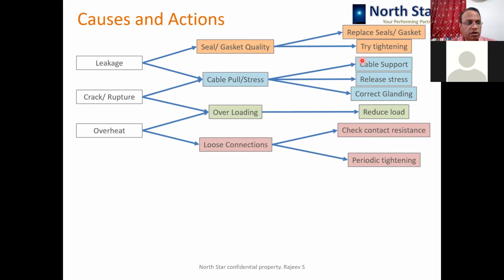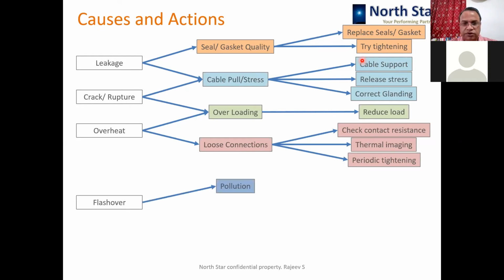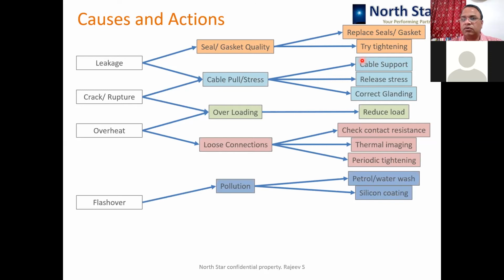So actually you don't run into this situation of overheating of the contact with that solution. Okay, flashover is because of pollution. So petrol or water wash of EHV bushings is recommended, and it is done also. You can also go with a coating of silicone, liquid silicone sprays on the bushings, so that is a permanent or long-term solution, because this coating once done on the bushing will not allow the pollution to affect the surface condition.